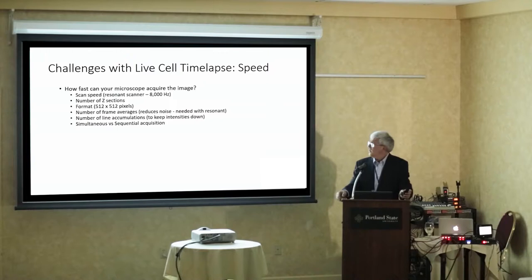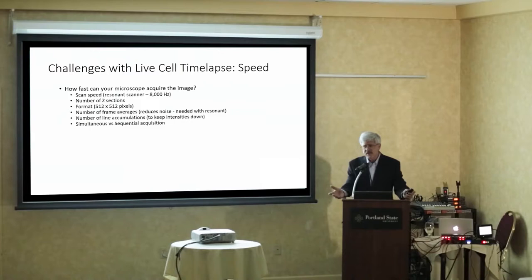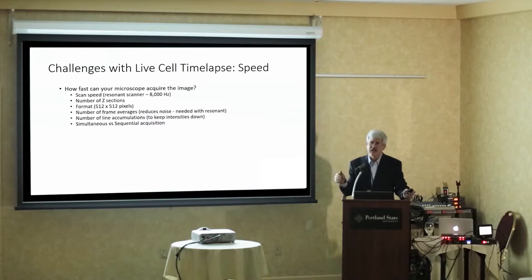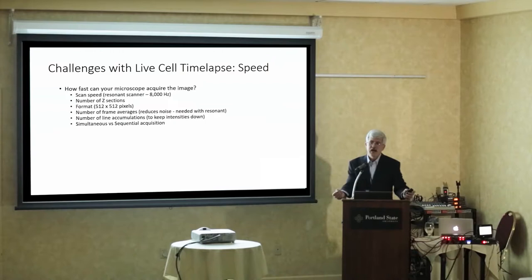Speed — how fast can you take your picture, and how fast do you need to? We have the speed of the scanner: a resonant scanner can go 8,000 Hz — that's 8,000 lines per second. Without a resonant scanner maybe the top is 1,000 or 1,400, while a good quality image might be at 700. So you're looking at 10 times faster using the resonant scanner. How many Z sections? If you do fewer, you can do it faster. Format: 512×512 takes half the time of 1024×1024. Number of frame averages reduces noise but takes longer.